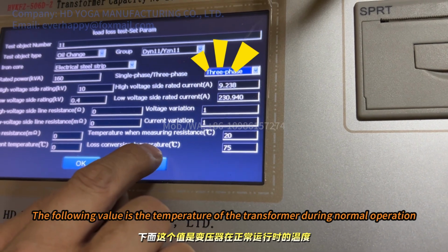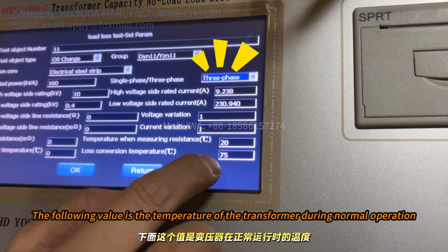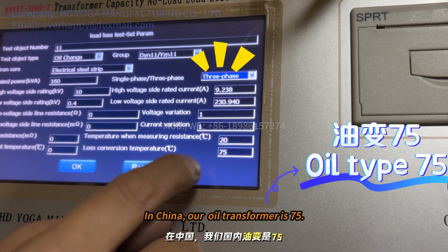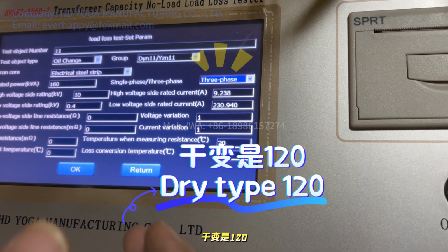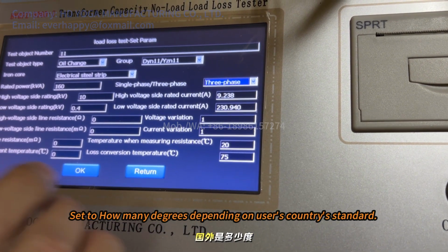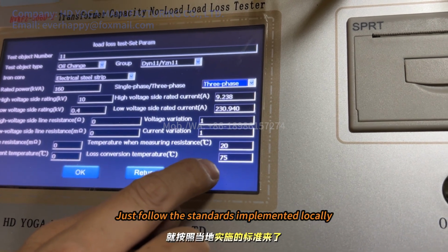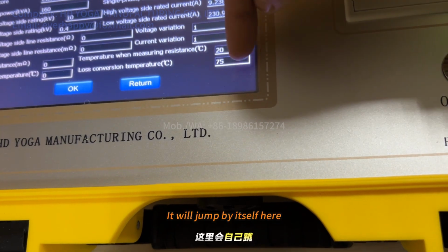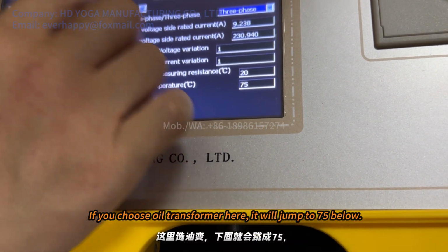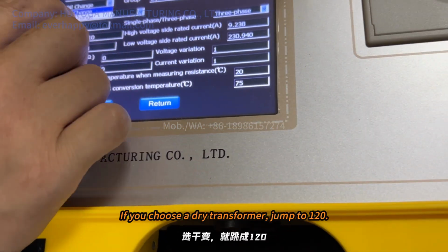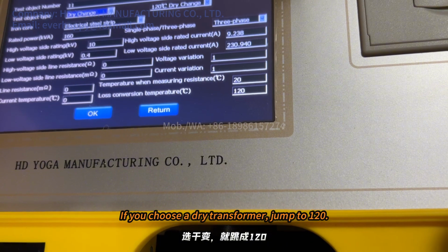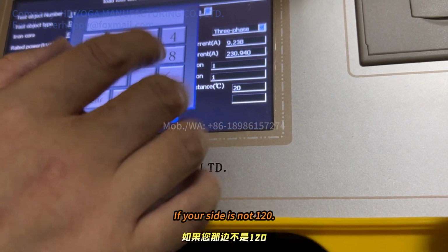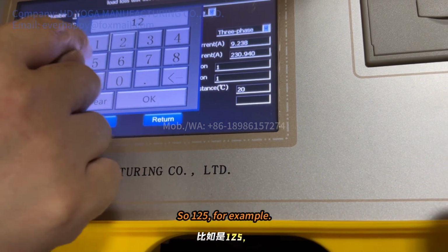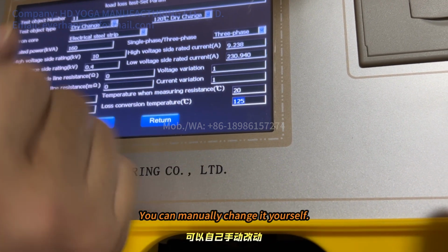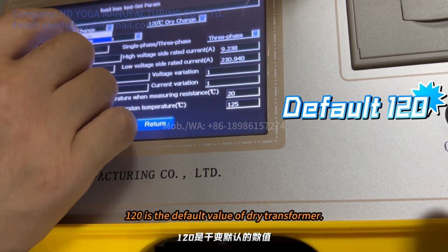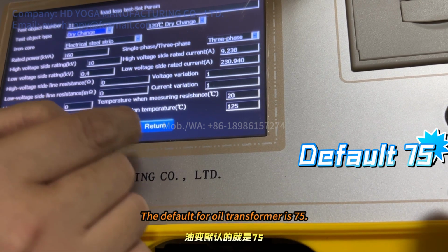The following value is the temperature of the transformer during normal operation. In China, our oil transformer is 75. Dry transformer is 120. Other temperatures are set depending on the user's country standard. Just follow the standards implemented locally. After choosing here, it will jump by itself. If you choose oil transformer, it will jump to 75 below. If you choose a dry transformer, it jumps to 120. This can also be changed. If your standard is not 120, say 125 for example, you can manually change it yourself. 120 is the default value of dry transformer. The default for oil transformer is 75.